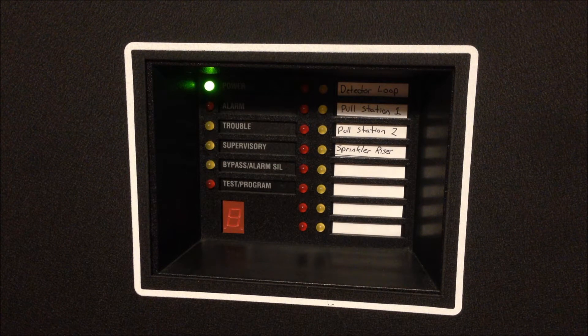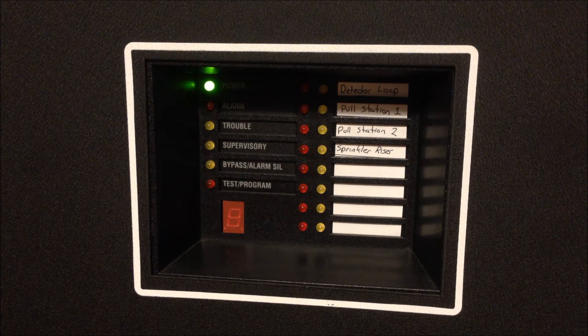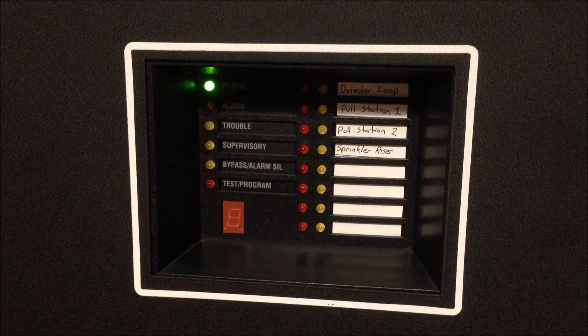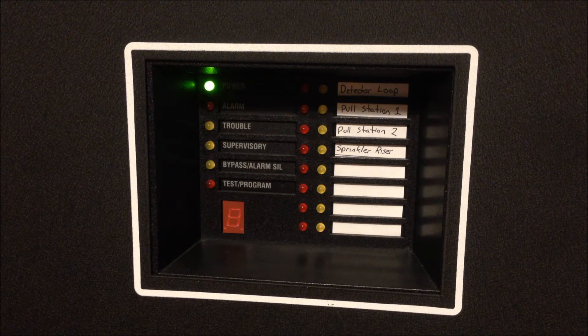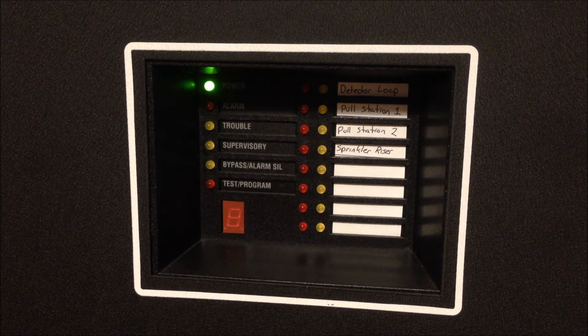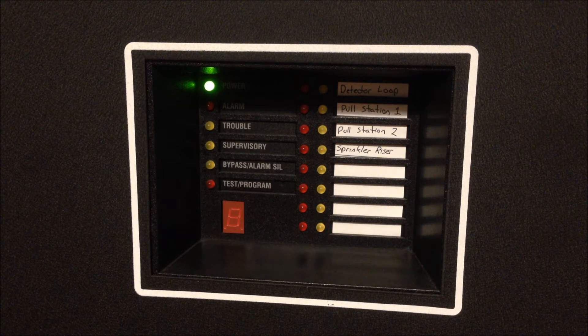So what the simple zone code feature allows the panel to do is to individually indicate which of the zones went into alarm based on the signal being outputted to the NAC circuits. In this case I have the Cerberus Pyrotronics chime that you'll see in a minute set on single stroke chime.